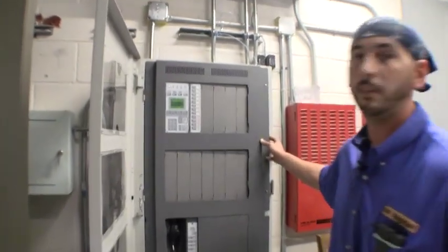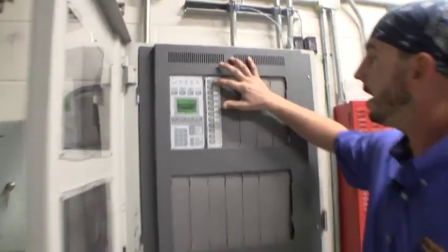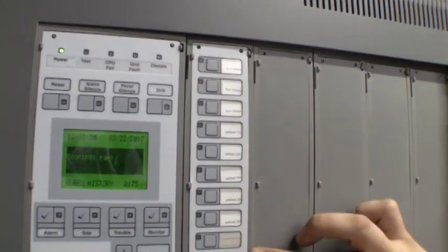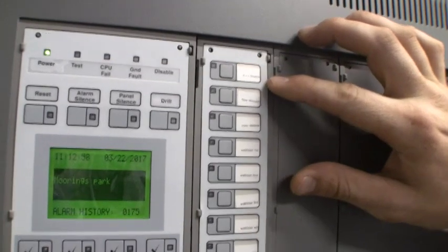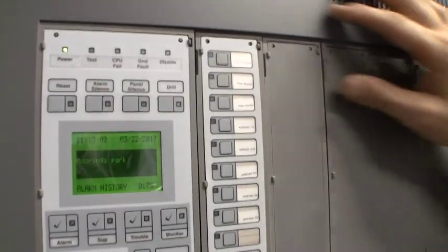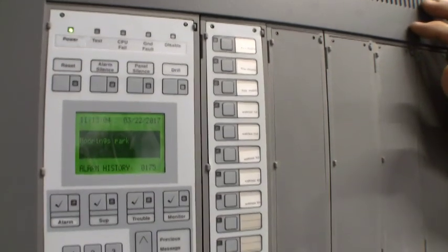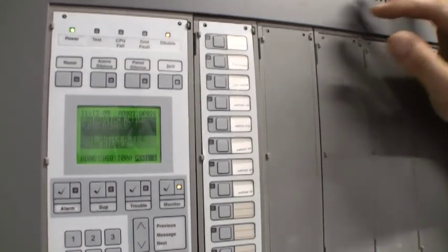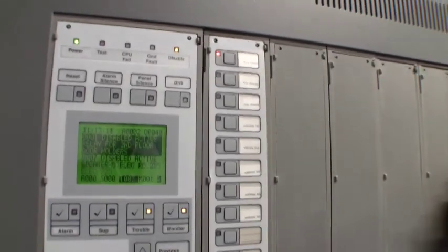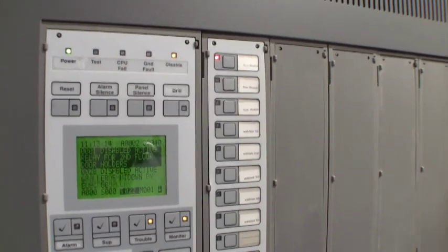This is the main master panel for this building. We have a couple of features on here — a set of switches each performing a different function. The top one would be for audio video disable. If you have a sprinkler contractor coming in doing a semi-annual on flows or any kind of annual inspections, you can hit that disable button and it'll stop the speakers and the strobes from deploying throughout the building.